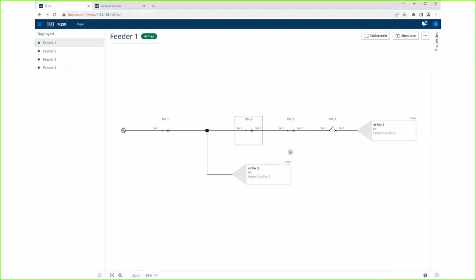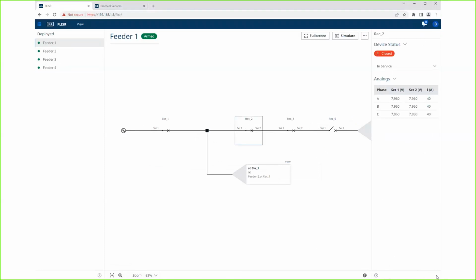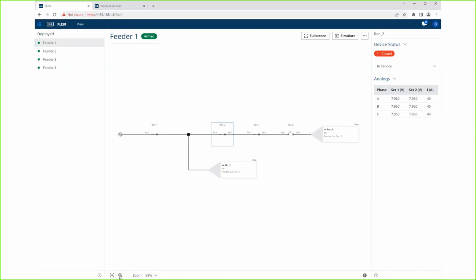It's going to send DNP controls. So we're going to put a permanent fault on feeder 1. All of these circuits are armed, so how does this work? So now when a fault occurs on feeder 1, it talks to feeder 4 and feeder 2 for real. So you can see it seeing lockout. It's issuing an open control to recloser 4, a close control to recloser 6.